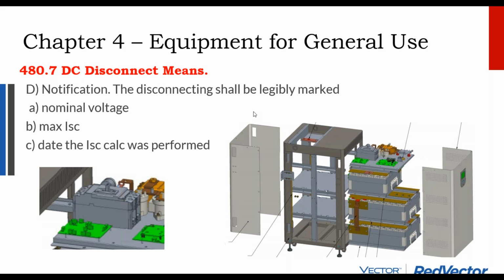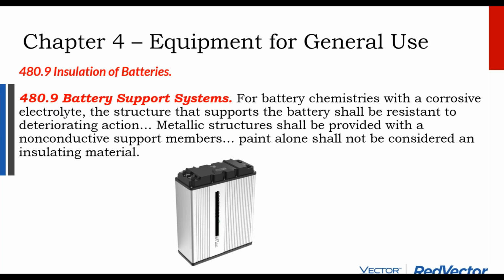Here's one of our batteries at Fortress, and you can see we have a built-in breaker into our battery pack. That's just a traditional 250 amp breaker at the top of the battery. And that would meet all of your code requirements without the need of having an external disconnect switch, which is a common requirement for solar, for example. And again, the battery industry is still in its infancy. And so I imagine these requirements will become better filled out in the future.